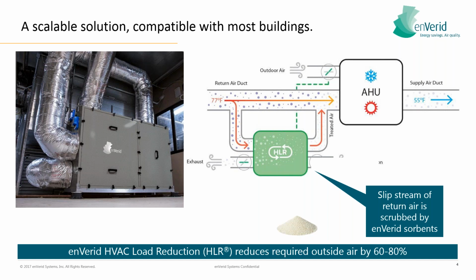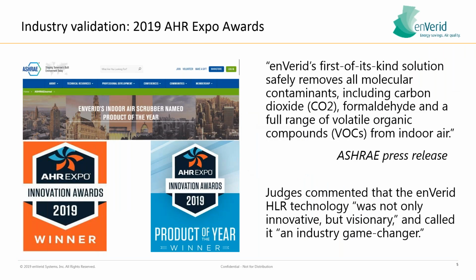And you can see there that we're a side stream air scrubber. So our device is not treating 100% of the return air, we're treating essentially just a small portion of it. That enables us to keep your downstream systems like your air handlers and whatnot of the same fan sizes. The net result of deploying our systems is that we're able to reduce outside air requirements by 60 to 80%. And you see the OPEX and CAPEX savings as a result of that as well.